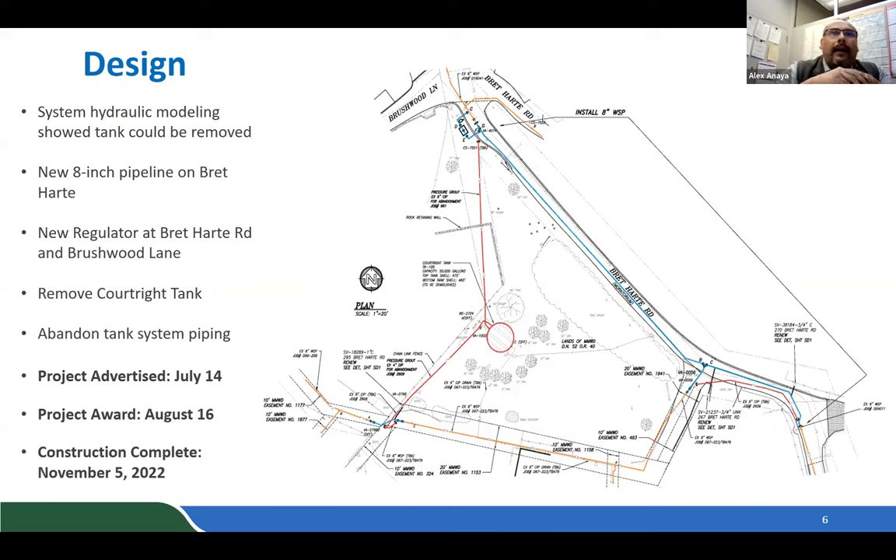Earlier in design, system hydraulic modeling showed that the Courtright tank could be removed from the system by connecting the larger Bret Harte system distribution main without affecting fire flow. This will be done by installing an 8-inch main along Bret Harte Road to the intersection at Brushwood, divorcing the pipe from the Courtright feed, and installing a pressure regulator valve to remove the tank from the system.